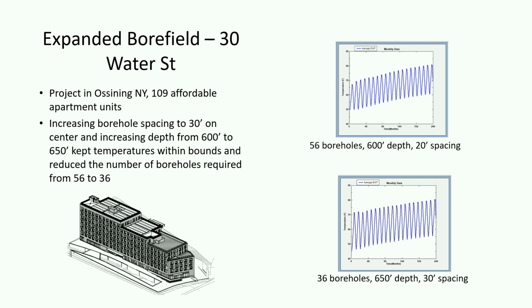So just a quick case study example. This is, stretching the definition of a high-rise building a little bit, but this is an affordable housing complex in New York. It's currently in design. As we're going through the design of this building, we develop our building energy model, we get the loads, we find that it does a bit more heating than cooling. So when we first plug in, we're maxing out our boreholes all tight together. We get 56 of them on our site, and we see an increase in our temperature year over year. Eventually we get outside of our bounds over 20 years.